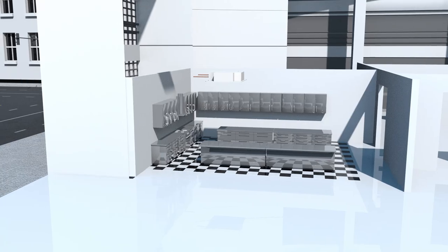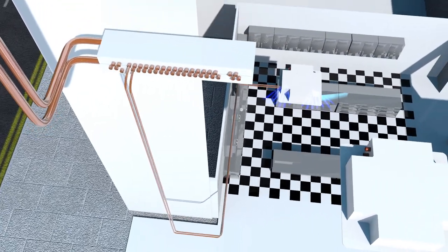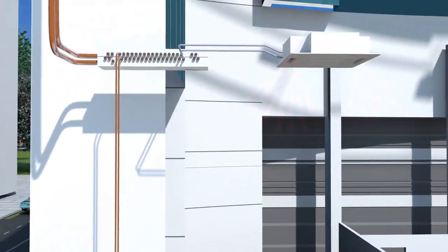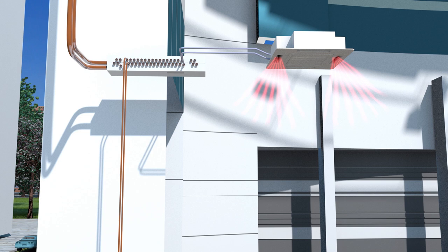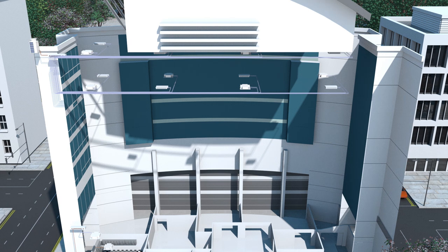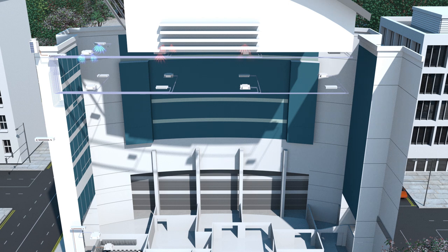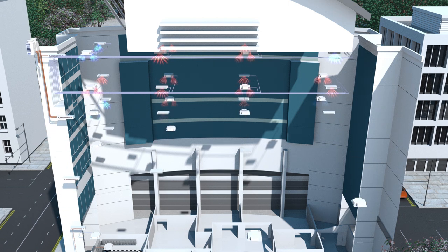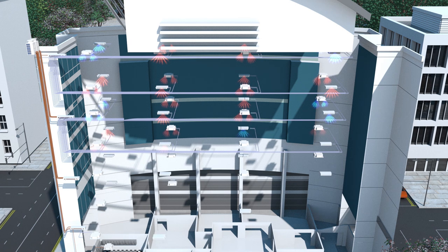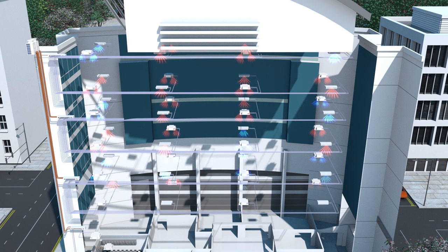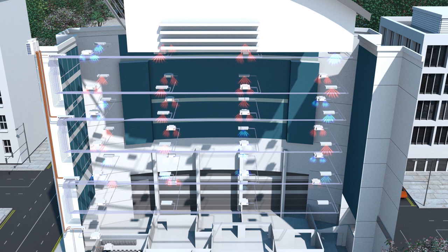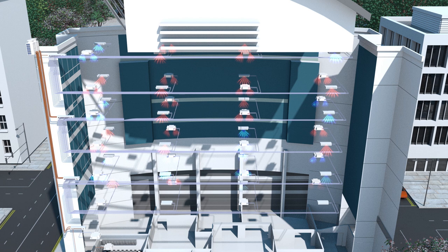Hybrid VRF can also offset the heating requirements of one room against the cooling requirements of another, and offers all of the advanced controls that CityMulti is renowned for, delivering a highly efficient mix of two technologies. The introduction of the new 16-port hybrid VRF means that up to 16 individual indoor units can be attached to each HBC controller, and two of these systems can be attached to the same outdoor unit, serving up to 32 indoor models. Now you're talking!